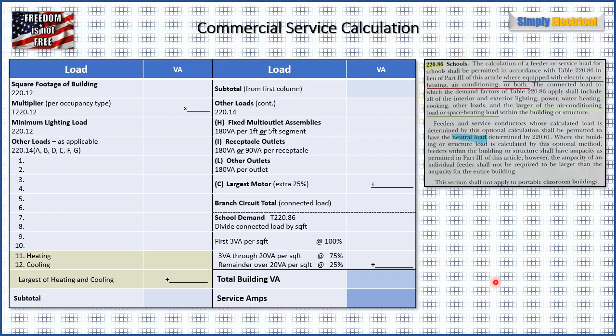Article 220, Section 86 is where we talk about schools, and this is the optional method of calculating a school service — we're under Part 4 in Article 220. It reads: '220.86 Schools — the calculation of a feeder or service load for schools shall be permitted in accordance with Table 220.86 in lieu of Part 3 of this article, where equipped with electric space heating, air conditioning, or both.' That's very important because we cannot use this optional calculation if we do not have at least one of either electric space heating or air conditioning. Otherwise we have to use the standard method.